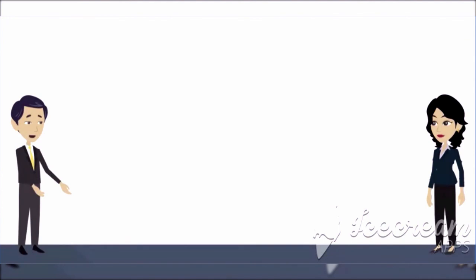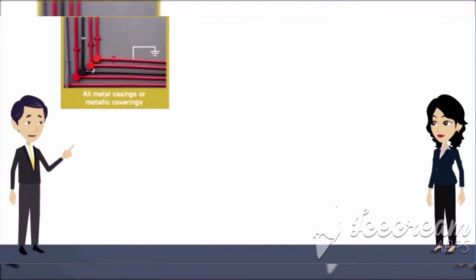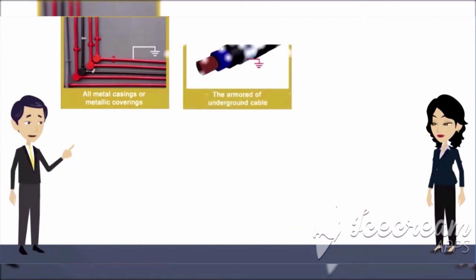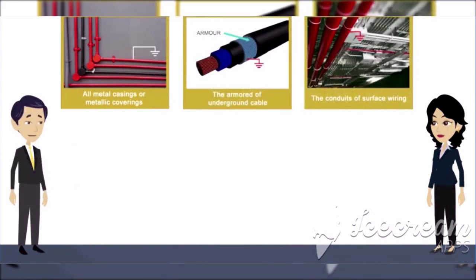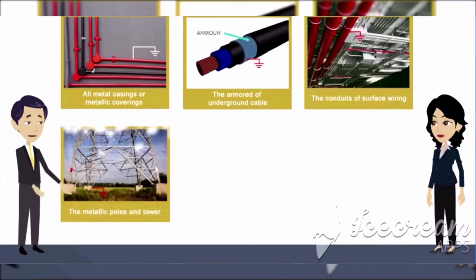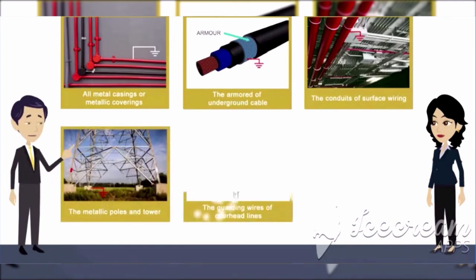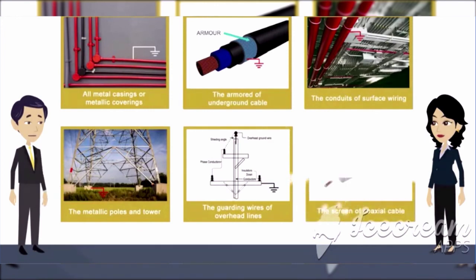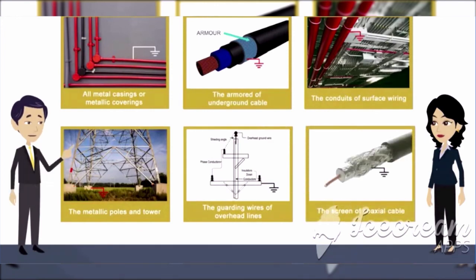Sure, they are all metal casings or metallic coverings containing or protecting any electric supply line or apparatus, the armored of underground cable, the conduits of surface wiring, the metallic poles and tower of overhead lines, the guarding wires of overhead lines, and finally, the screen of coaxial cable. All right, but Mayank, I can see that the cable has so many parts or layers. Aren't all of those connected? You are right, but when we say screen of coaxial cable, it refers to the braided part that can be additionally connected to the ground. And yes, that was all.